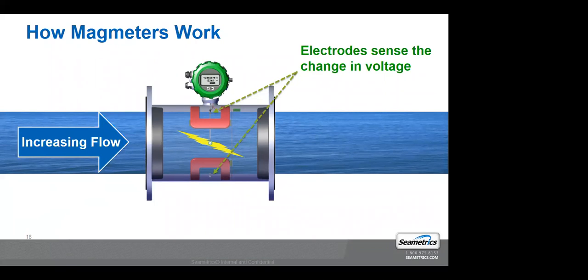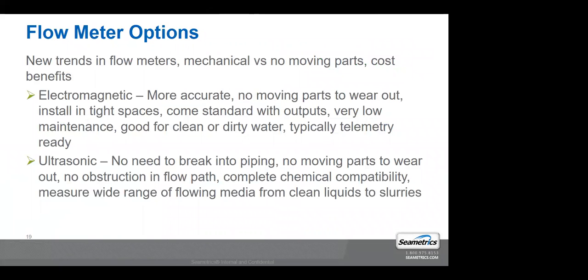This principle of how mag meters work applies to all manufacturer mag meters, all types of mag meters. It's a little bit different when it's an insertion mag meter. There might be one magnet in it instead of several electrodes, but the principle is still the same of how it's working.